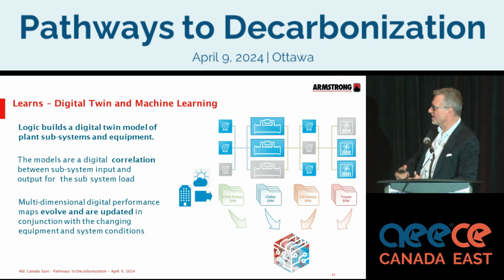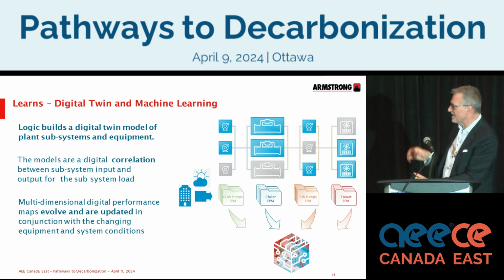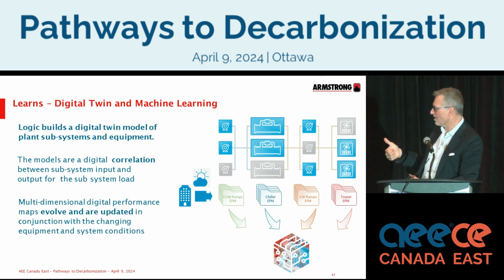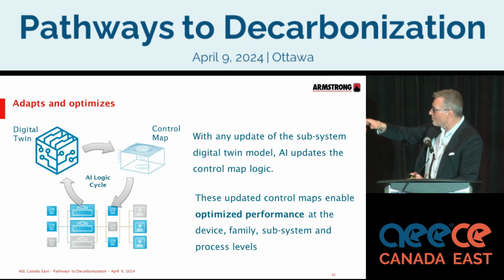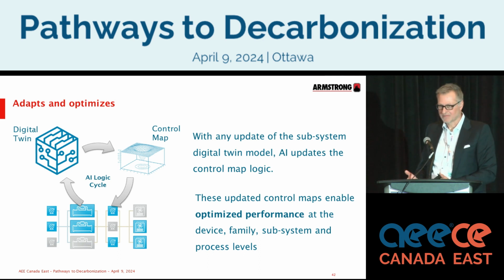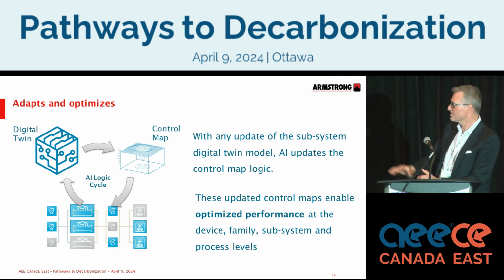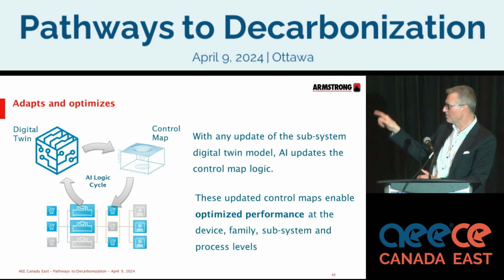So with digital twin and machine learning, the equipment starts to learn how it's operating, and that learning then updates those digital maps. The challenge is that you've got digital updates on your pumps, your chillers, and your towers, and that becomes a multi-dimensional digital performance map. The last time we tried to calculate it, it was actually 26-dimensional. So there are 26 dimensions in that matrix in terms of the data available for outlining the performance of the system. But once it collects that data, it's able to adapt, and it continuously commissions, recommissions, or improves the performance of the system. That's where the logic comes in.